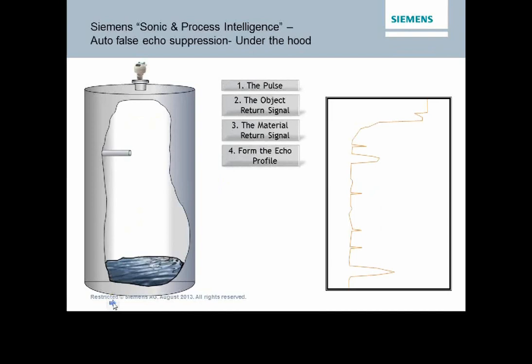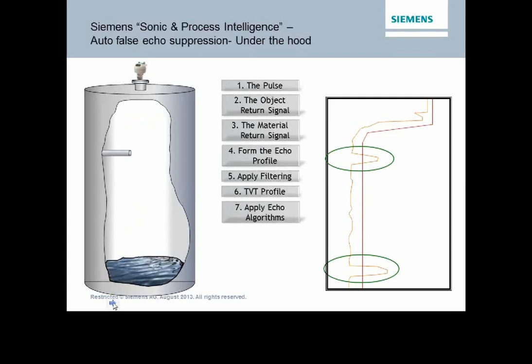So what we do is we actually send out a pulse, whether that's radar or ultrasound. We look for that object return signal, and we form an echo profile. We apply some filtering, which we call the dynamic TVT, or time varying threshold, and we take a look at the echoes. Anything above that threshold, we actually analyze. We analyze those with a number of echo algorithms, which are specific to the process and optimized for the process.